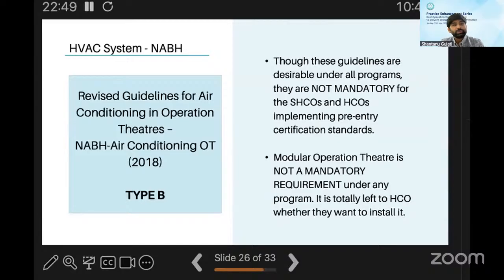So with respect to the NABH 2018 revised guidelines for air conditioning in operating theaters, the modular operation theater is not a mandatory requirement. So basically whatever panels I talked about are not mandatory. What is acceptable is if you can arrange a system which is seamless and non-porous and maintain it, whether it is done by vitrified tiles with grouting or a punched surface with paint application, which is antibacterial. With respect to the air management, AHU and HVAC systems are recommended even if you are doing a pre-entry certification standard. There it is not compulsory, but it is still recommended.